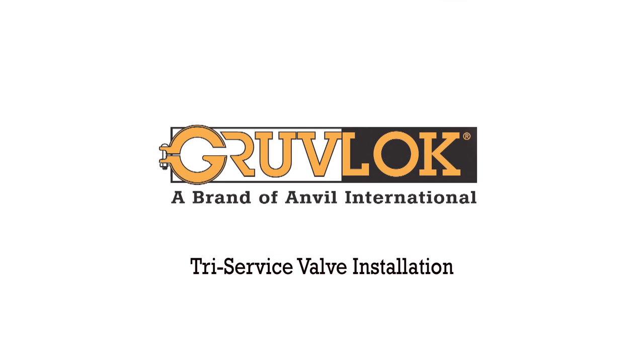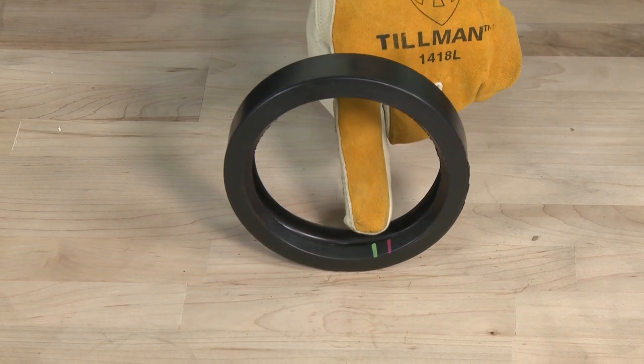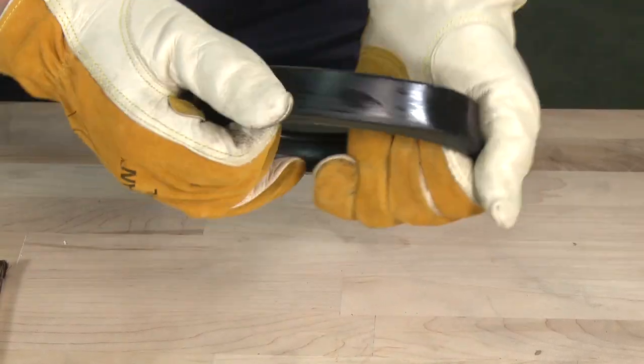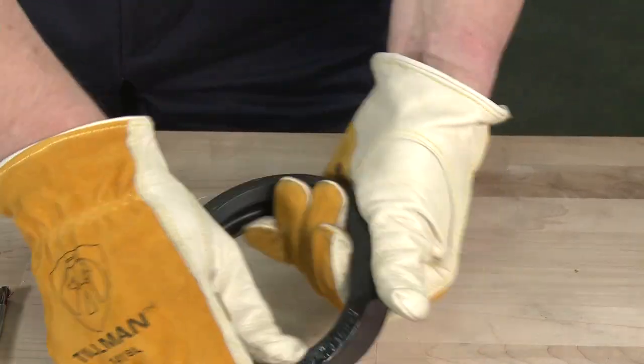Tri-Service Valve Installation. Check the gasket to be sure it is compatible for the intended service. Apply a thin coat of Gruvlok lubricant to the outside and sealing lips of the gasket. Some applications require lubrication of the entire gasket surface.